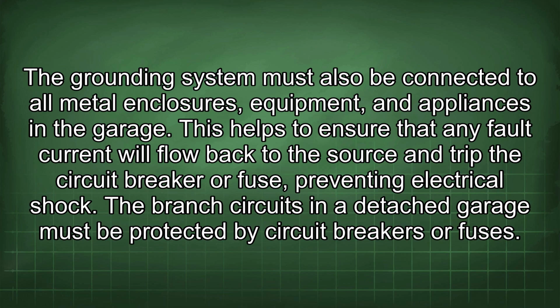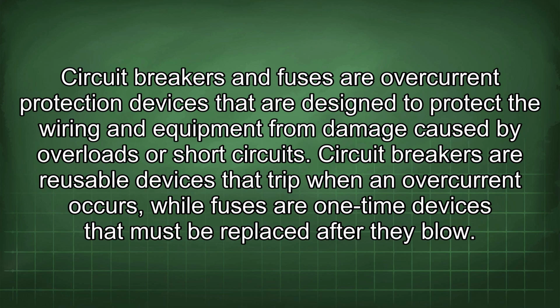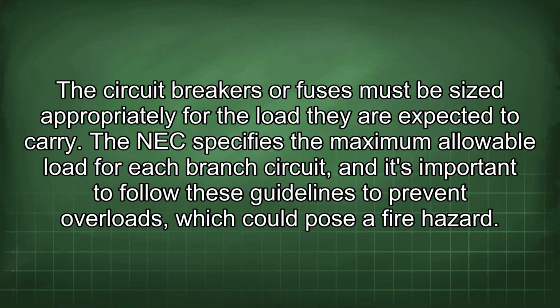The branch circuits in a detached garage must be protected by circuit breakers or fuses. Circuit breakers and fuses are overcurrent protection devices that are designed to protect the wiring and equipment from damage caused by overloads or short circuits. Circuit breakers are reusable devices that trip when an overcurrent occurs, while fuses are one-time devices that must be replaced after they blow. The circuit breakers or fuses must be sized appropriately for the load they are expected to carry. The NEC specifies the maximum allowable load for each branch circuit, and it's important to follow these guidelines to prevent overloads, which could pose a fire hazard.